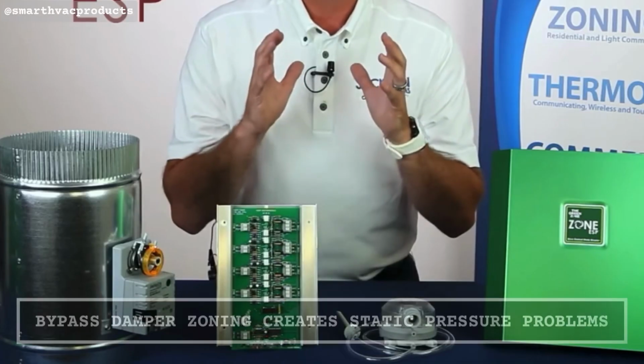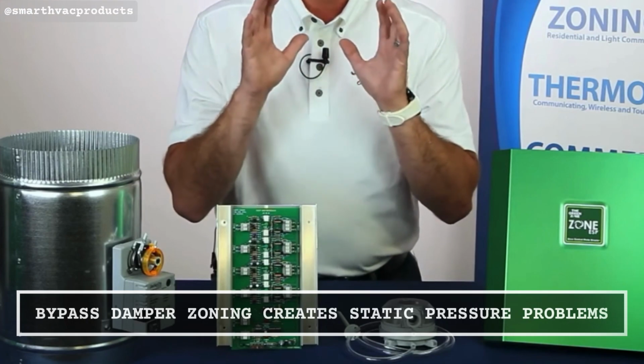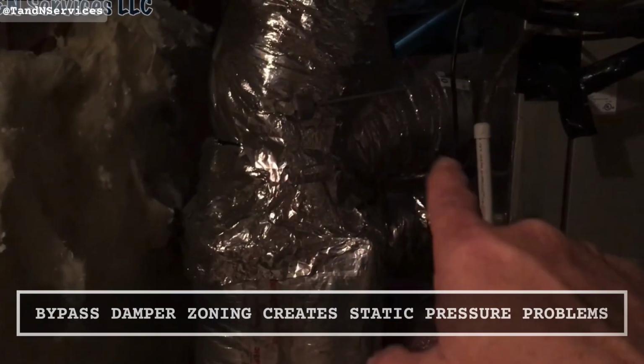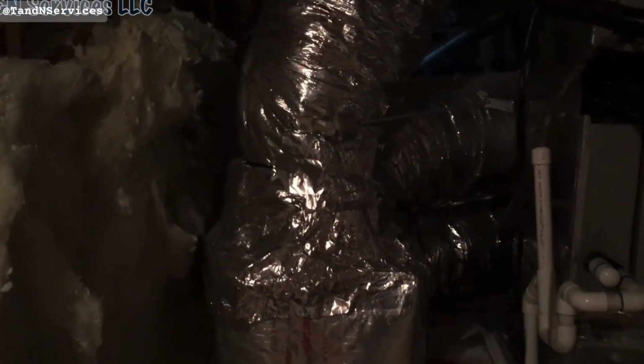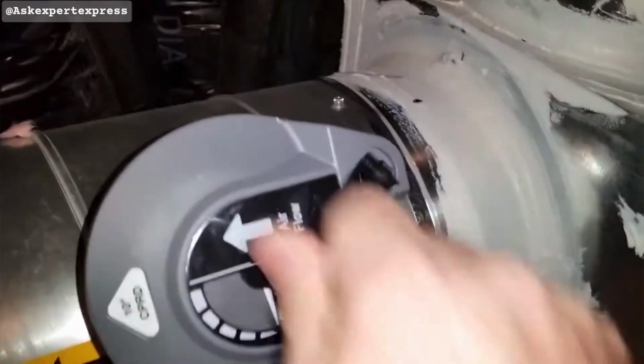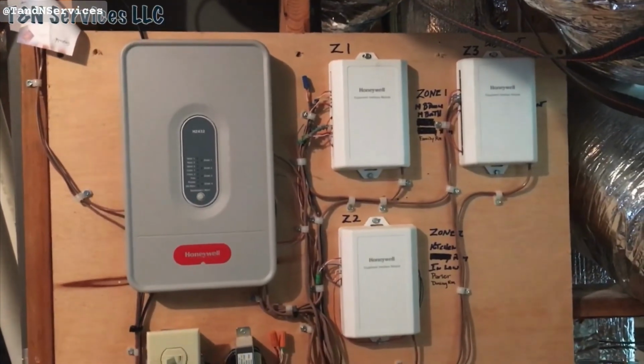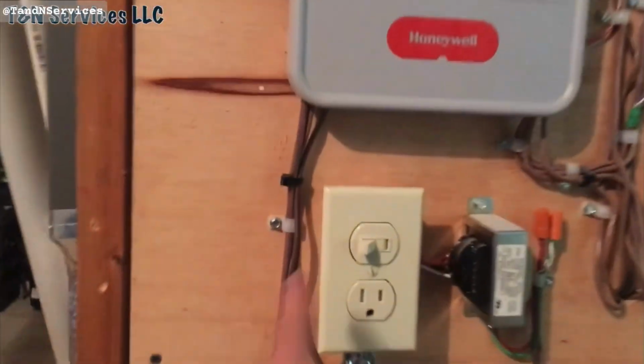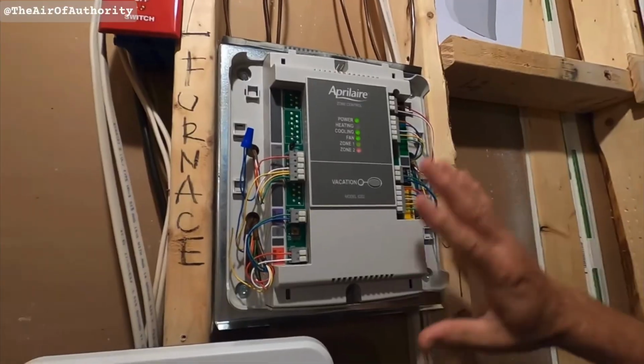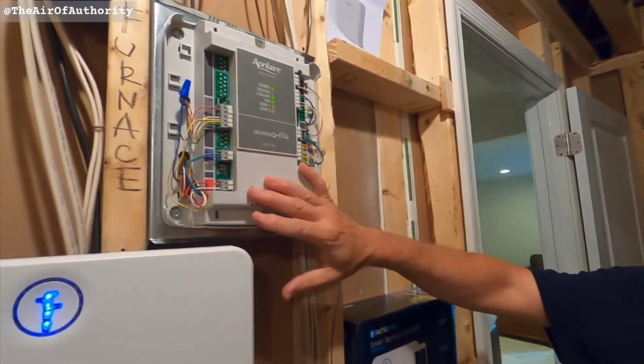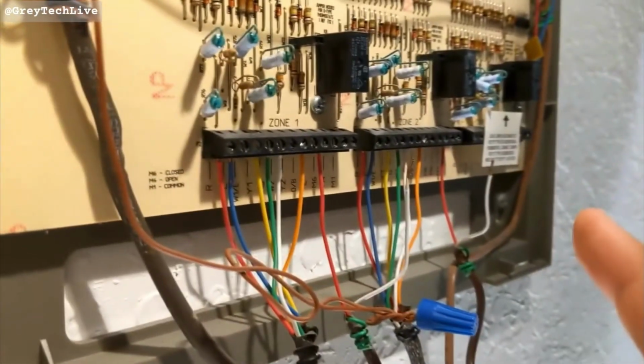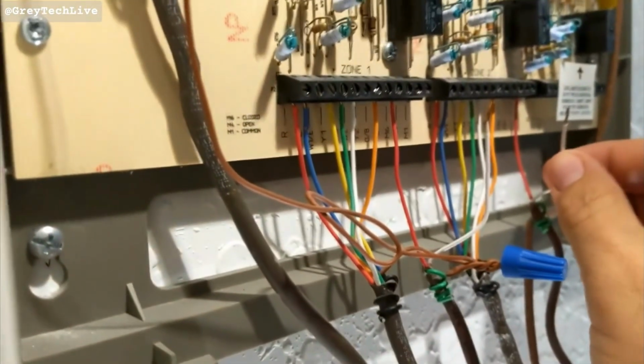Number 15. Bypass damper zoning systems cause more problems than they solve. The bypass damper, which dumps unused supply air back into the return when zones close, raises static pressure, drops latent heat removal, and short cycles the compressor. I used to recommend bypass zoning on most retrofit jobs about 15 years ago, until I started seeing the failure pattern on systems I'd installed 3 to 4 years earlier. Now I tell homeowners with comfort imbalance problems to fix the ducts first and only consider real VAV zoning with no bypass as a last resort. If a contractor quotes you bypass damper zoning, ask him about the static pressure implications and watch how he answers.